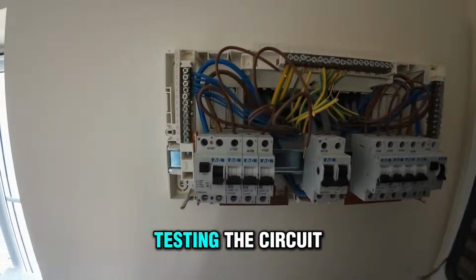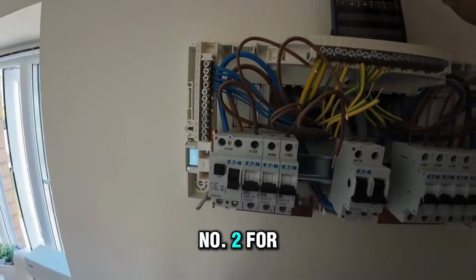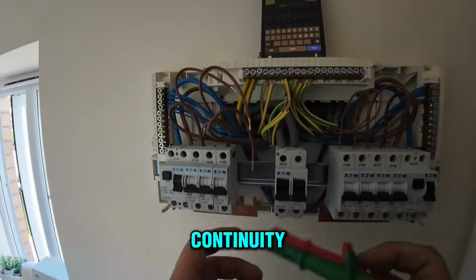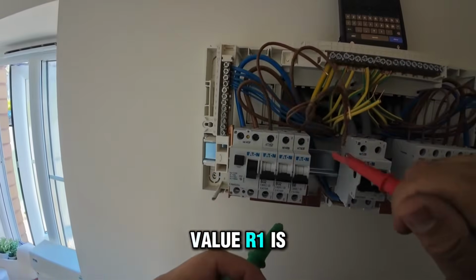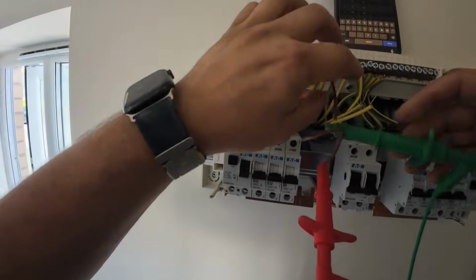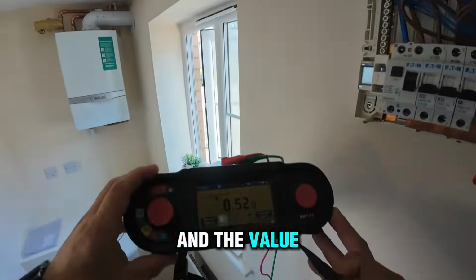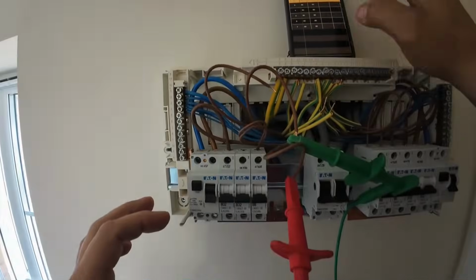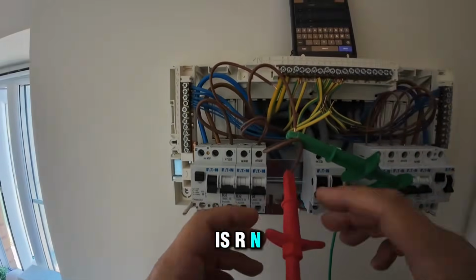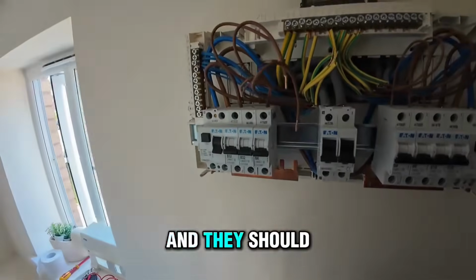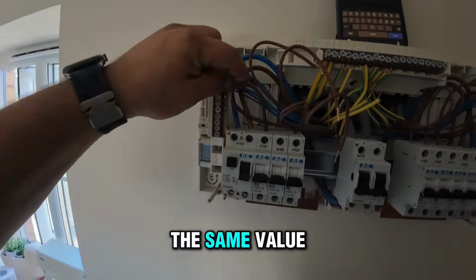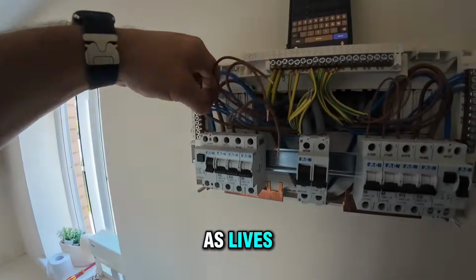And we are testing circuit number 2 for now for ring continuity, and that's the R1 value. R1 is live, so end to end. And the value is 0.52. The next one is Rn, which is the neutral. And they should give us exactly the same value as the lives.